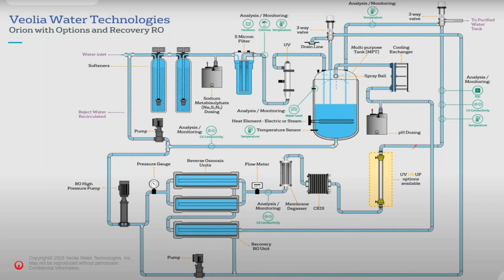The other thing we do is, conventionally during recycle, you would run 100% of the flow. So if this was a 4 meter cubed an hour system, you would run at 4 meter cubed an hour in recirculation. We generally, when it goes into recirculation, drop that by 50% by using a VFD on the pump here. So the flow rate reduces to about half. So again, you're saving electrical energy during that recycle phase as well, but still maintaining your velocities through the pipeline in accordance with the ISPE guidelines and recommendations for turbulent flow within pipelines.